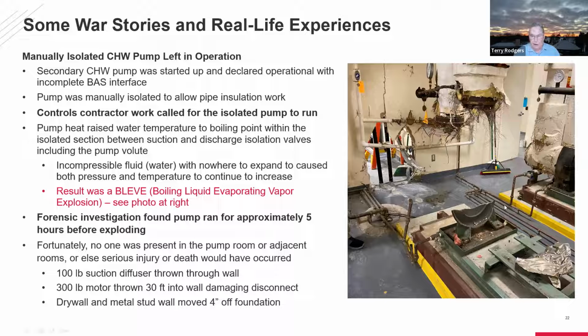What you see here is what's left of the pump volute. The hole here is where a suction diffuser, which weighed 100 pounds, was thrown through the wall and knocked the computer room air conditioner off on the other side. This is where the motor had been bolted; it sheared it completely off the base and threw the motor about 30 feet, and it wasn't skidding along the floor because it hit a disconnect at about a height of 3 feet. So it's quite a lot of energy that was released. This was only a 30 horsepower and 750 GPM pump, not a big deal.